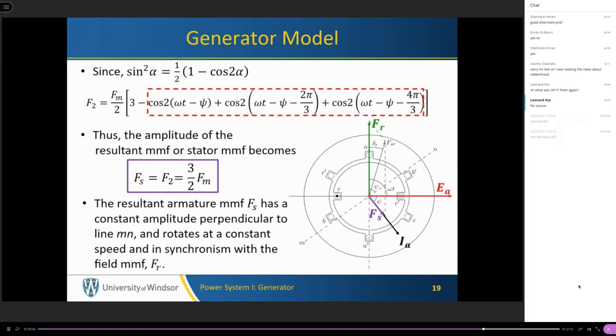This is in order to understand how the stator magnetic field interacts with the rotor magnetic field. We cannot have stationary magnetic fields and convert them to a rotating magnetic field; we have to unify the frame that we are studying or working with. Previously the generator was unloaded, disconnected from the grid, and that is why we had only FR, the magnetic field from the rotor. When the generator supplies a load or is connected to the grid, it will generate current, and this current will generate a resultant magnetic field perpendicular to the line MN, represented by FS. Any questions?